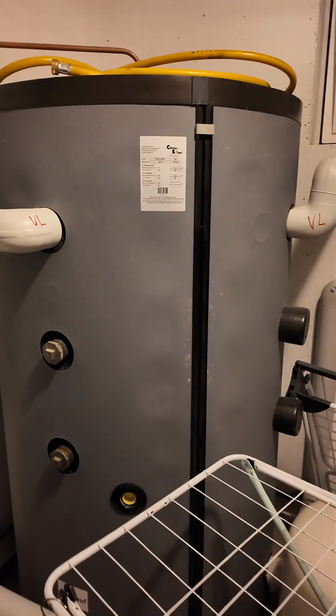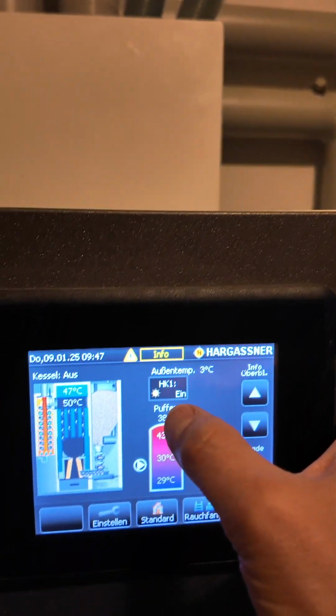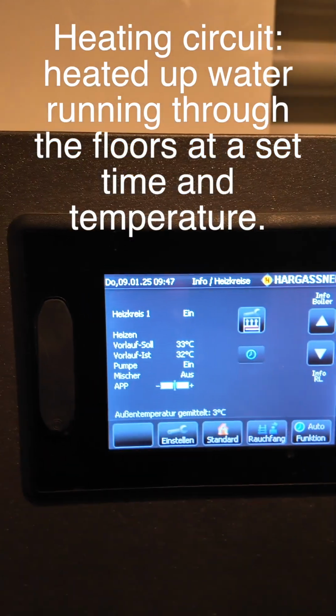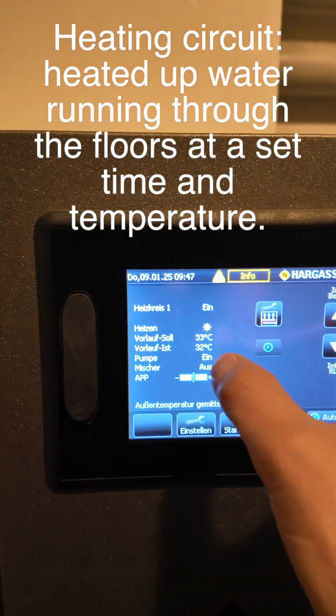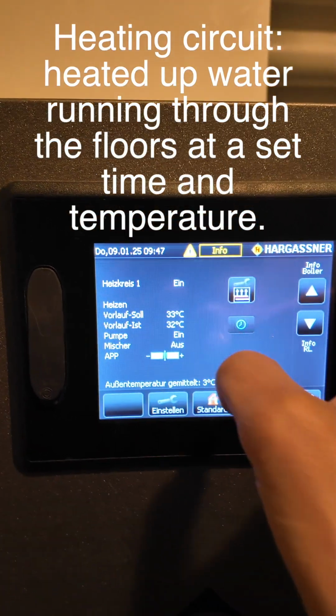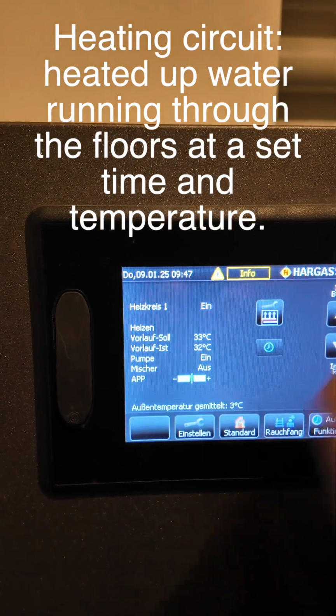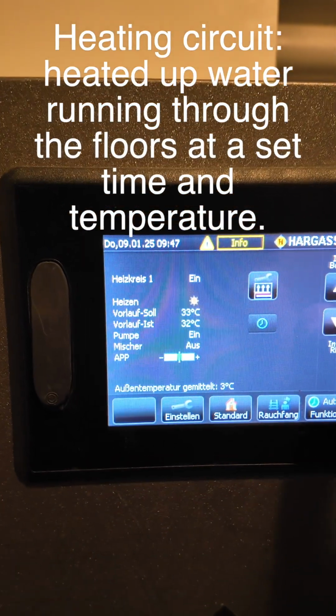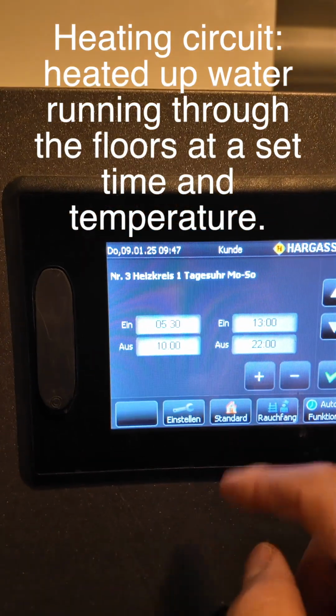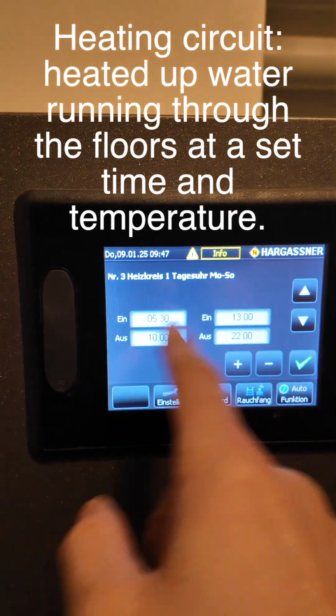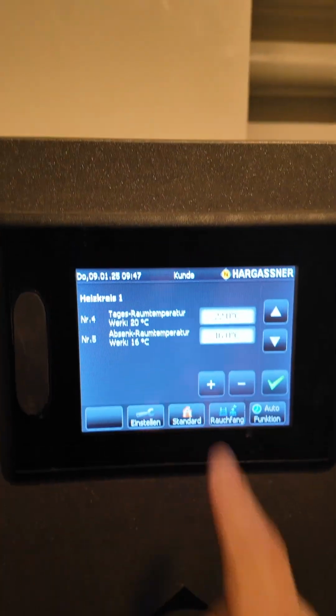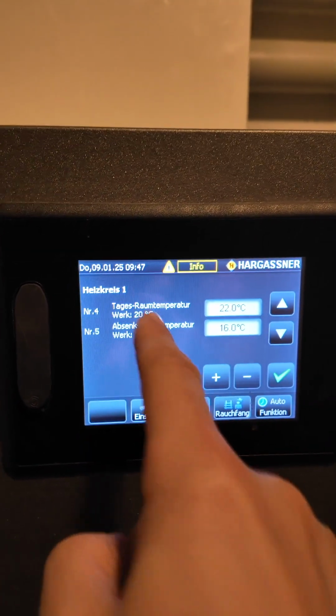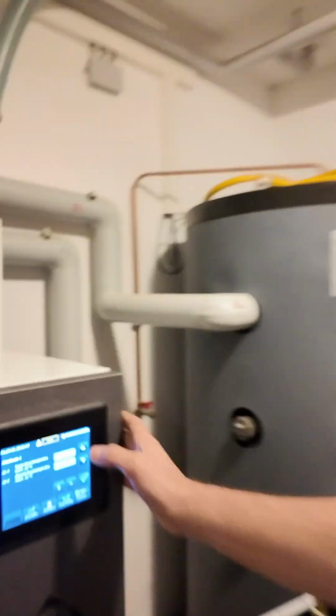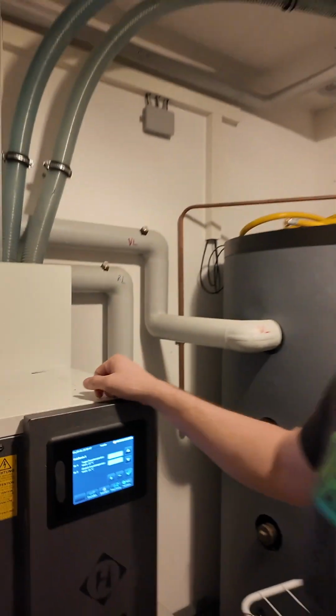So far, so good. Now what you have is what they call a Heizkreis, or the heating circuit. So the heating circuit, what you need is some kind of set point temperature. So right now it's at 33 degrees Celsius set point temperature. If we go to the parameters, you can, of course, set the times, that's easy. But then you also have to choose a room temperature during the day. This room temperature during the day is actually not 22 degrees. That's not what it is.